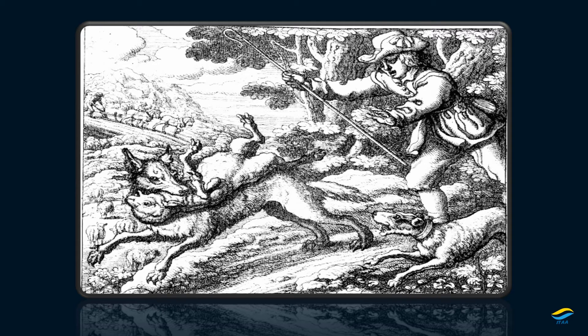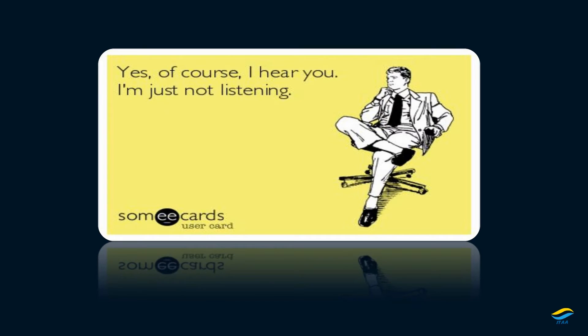While programming alarms, you have to stop and think before going ahead. Consider safety — it's really important. For anything critical, we need to put an alarm there for sure. But it doesn't mean we need to put an alarm for everything that is unusual. There are too many things that don't hurt the process. If you give the operator too many alarms and notifications, they will possibly stop looking at them properly, and if something critical happens, they might miss it and not be able to respond properly.